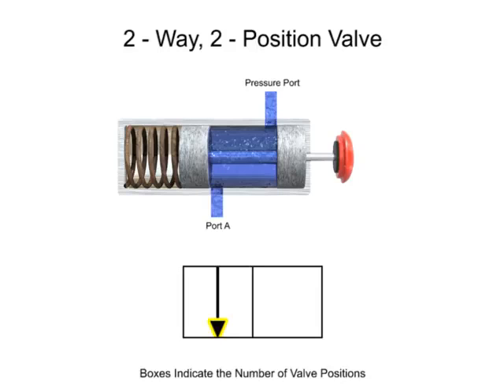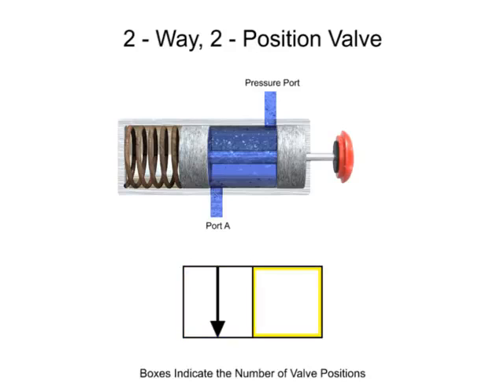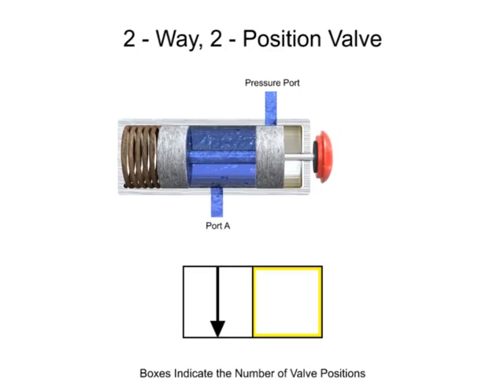A solid arrow indicates the direction of liquid flow. The first position of this valve allows fluid to flow from the pressure port to port A, so an arrow is drawn in the first box to indicate fluid flow. A T indicates that a port or way is blocked or closed. This valve's first position has no ports blocked, but its second position blocks both. The second box corresponds to the second position of the valve. Therefore, two T's are added to illustrate the lack of fluid flow in the second position.